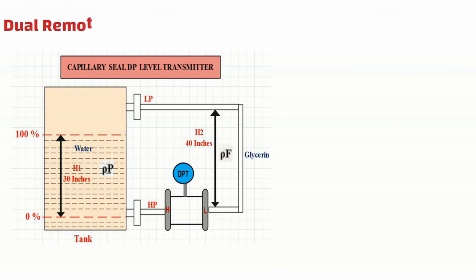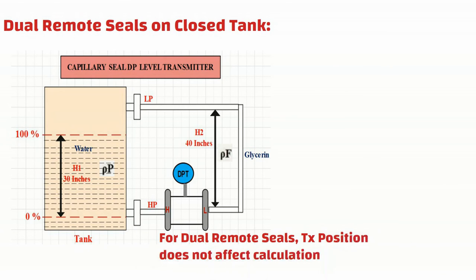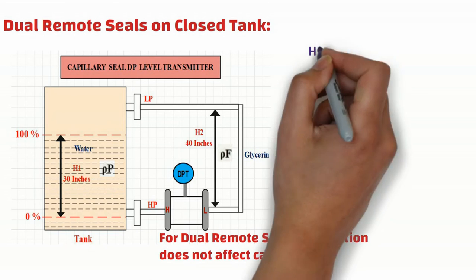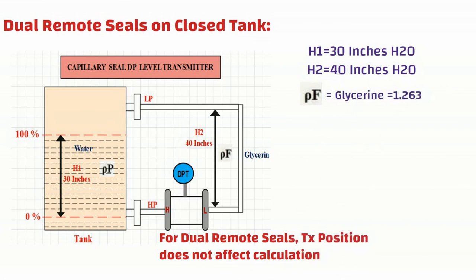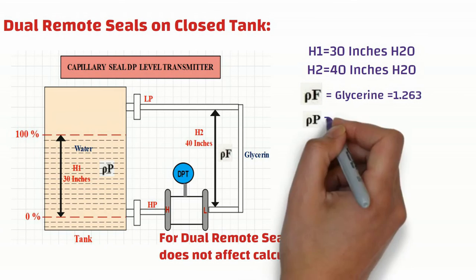As you can see from the diagram, this is an example of a dual remote diaphragm seal on a closed tank. It is important to understand that the transmitter position does not affect the calculation when dual remote seals are used — it does not matter whether the transmitter is below or above the bottom tap. The LRV and URV are the same for all three conditions. In this example, the distance between the bottom tap and maximum level height is 30 inches, and the elevation distance between the lower seal tap and upper seal tap is 40 inches. The remote seal is filled with glycerin with a specific gravity of 1.263, and the process fluid is water with a specific gravity of 1.